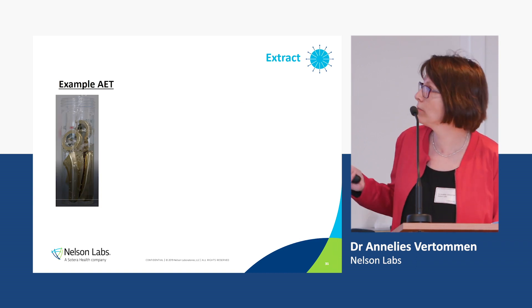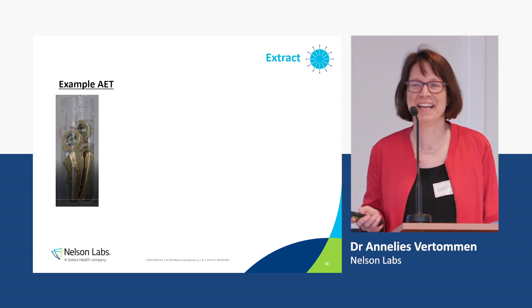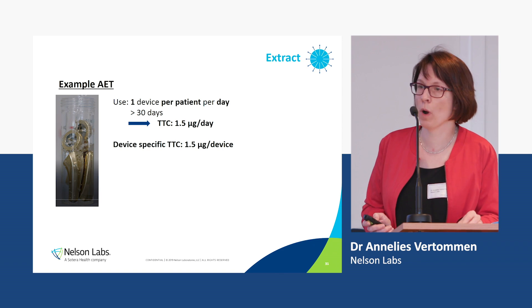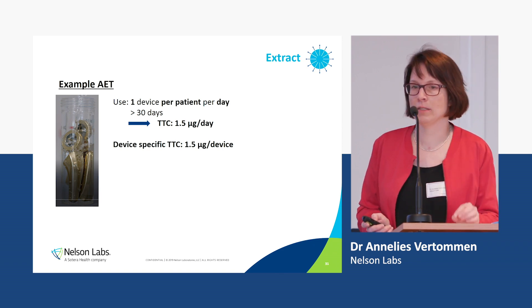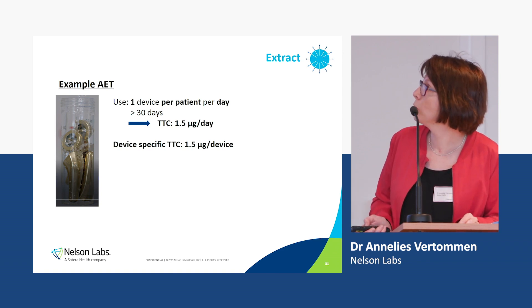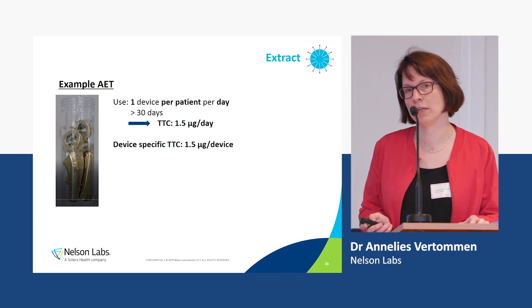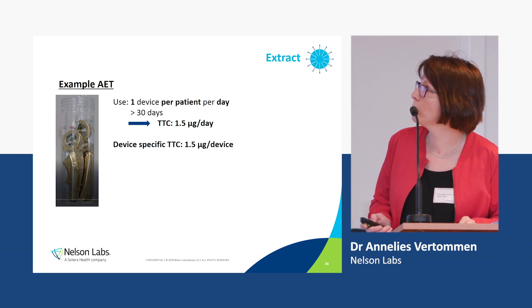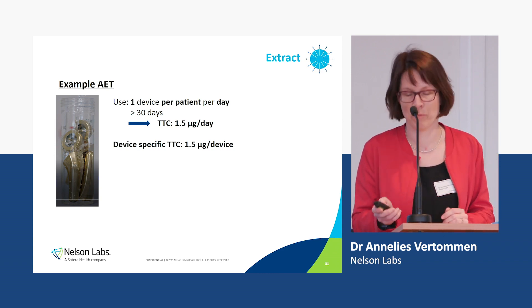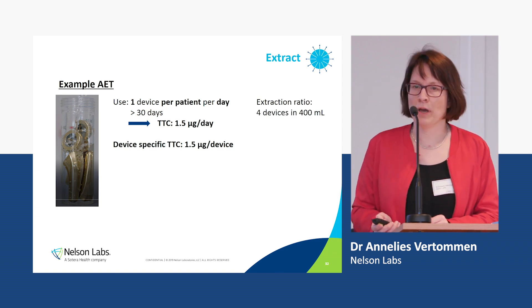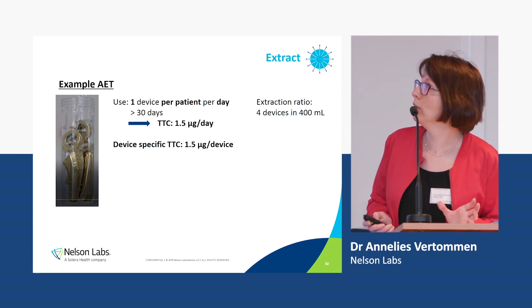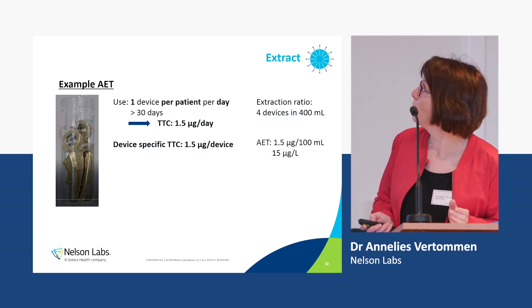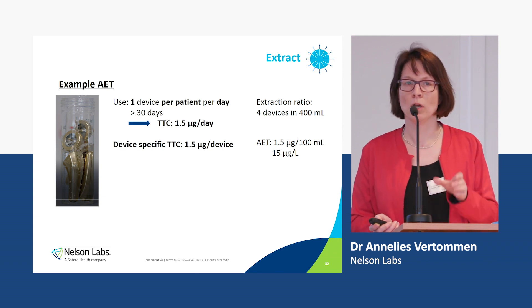An example of calculation: let's look at an implant device. What's important is knowing how much of your device is used in one patient in one day — here it's only one. The time of contact is more than 30 days. So you go from your TTC described in ICH M7 to a device-specific TTC. It's a simple calculation: 1.5 micrograms per day, one device used per day — so 1.5 micrograms per device. Then you have your extraction ratio: four devices extracted in 400 ml, meaning your analytical evaluation threshold is 1.5 micrograms in 100 ml.